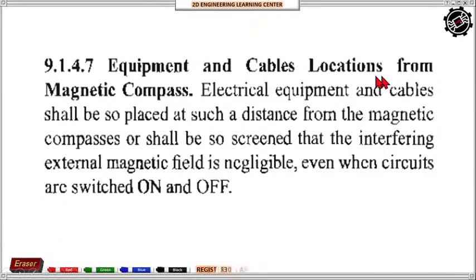Equipment and cables location from magnetic compass. No, so bakit ito mahalaga? Because there will be an electrical interference, no, of the navigation system of our ship, no, if we don't have proper distance, no. So electrical equipment and cables shall be so placed at such a distance from the magnetic compasses or be screened that the interfering magnetic field is negligible, even when the circuits are switched on and switched off. So alam natin na yung ating mga wires will have its own magnetic field, no? Kapag sobrang lapit siya, so it may interfere with our navigation system. So kaya it is properly insulated, no, screen, or may tamang spacing.